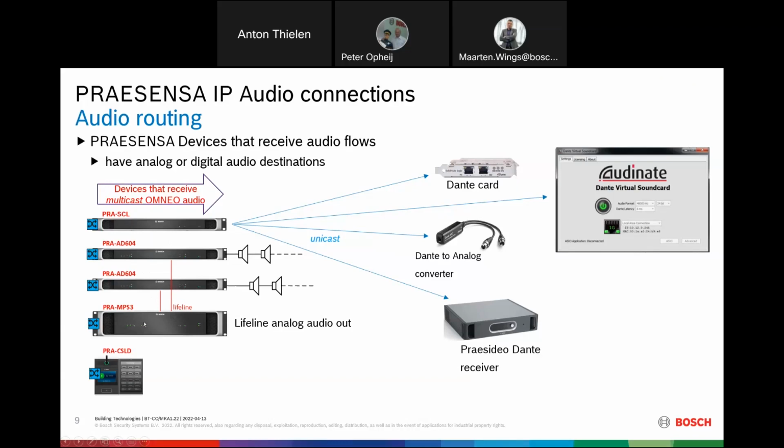Yeah, so the multifunction power supply has more functions than only powering the devices. It is also there providing the voltage, but it's also there to give this lifeline audio to the amplifiers in that case of a backup. And then you have the call station loudspeaker to listen to chimes and messages.